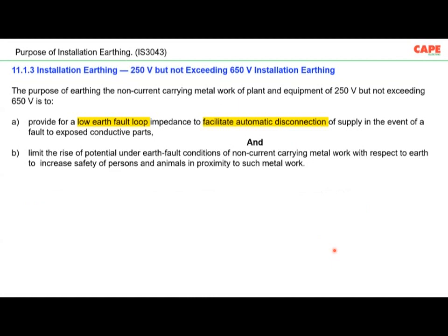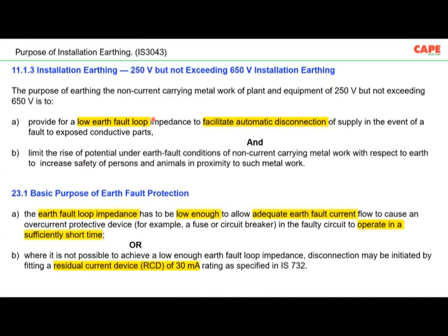The purpose of earthing the non-current carrying metal plant and equipment of a 250 volt but not exceeding 650 volt system is, please read the highlighted portion: provide a low earth fault loop impedance to facilitate automatic disconnection of supply. Then the second purpose is to limit the rise of potential. So basically, earthing in an installation has two purposes. One is to make a very low fault loop impedance connection so that your equipment is able to disconnect in case of a fault. And the second is to reduce the touch voltage.